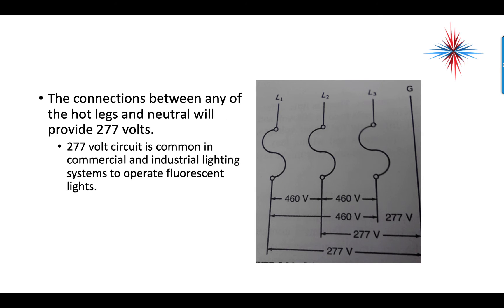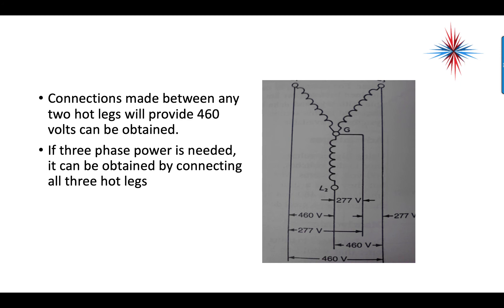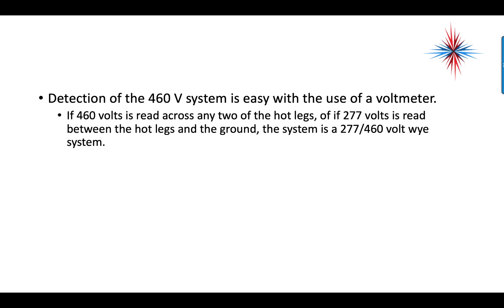Connections between any hot leg and neutral provide 277 volts. 277 volts is common in commercial and industrial systems to operate fluorescent lighting — the fluorescent lights in large shopping malls, department stores, factories, and large commercial applications such as schools are not 120 volts; they are 277 volts. Connections between any two hot legs provide 460 volts, and three-phase power is obtained by connecting all three hot legs. Detection of a 460-volt system is easy: if 460 volts is read across any two hot legs, or 277 volts is read between a hot leg and ground, the system is a 277/460-volt Y system.